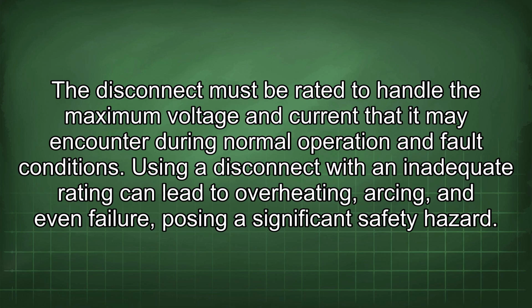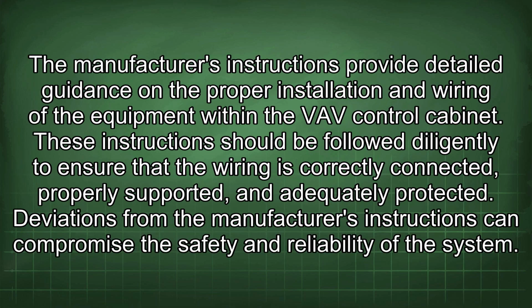The manufacturer's instructions provide detailed guidance on the proper installation and wiring of the equipment within the VAV control cabinet. These instructions should be followed diligently to ensure that the wiring is correctly connected, properly supported, and adequately protected. Deviations from the manufacturer's instructions can compromise the safety and reliability of the system.